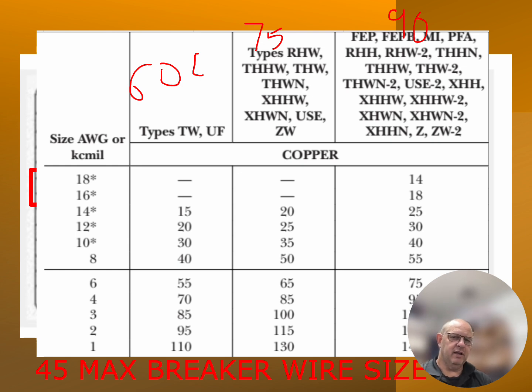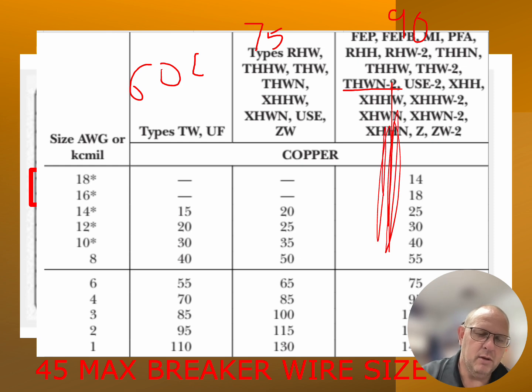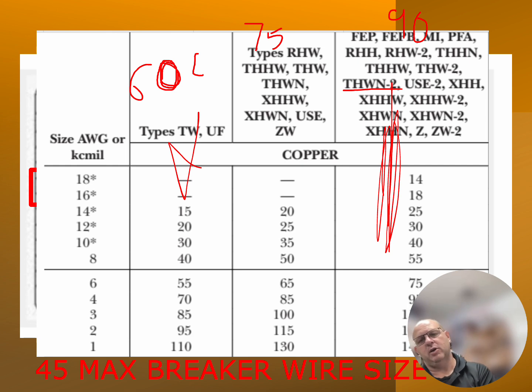So even if I come over here and I decide that I'm using a THWN wire that's good for outdoor use, I cannot base the amp draw off of this particular column because I don't know the termination degrees that wire is going to be landed on. So we will use the first column. A good rule of thumb is always use that first column when you're doing your amp draws so that you don't mess up and put a wire size in that's going to be too small for this. Okay, so going back to that, we're going to be looking at this first column.